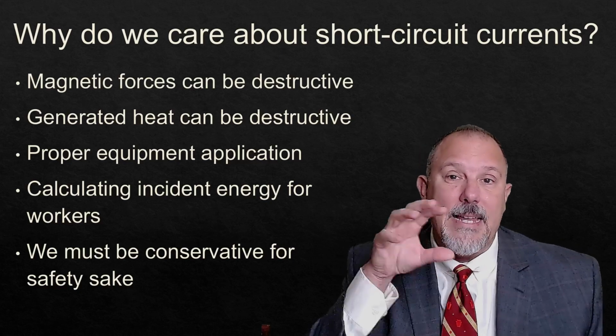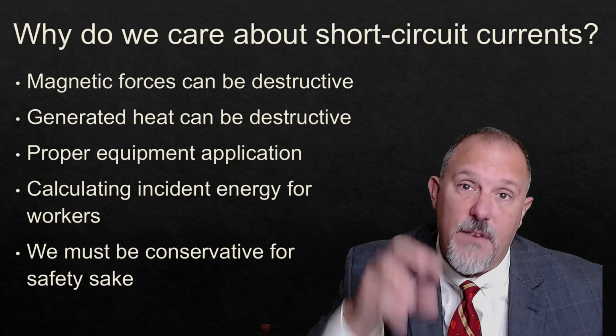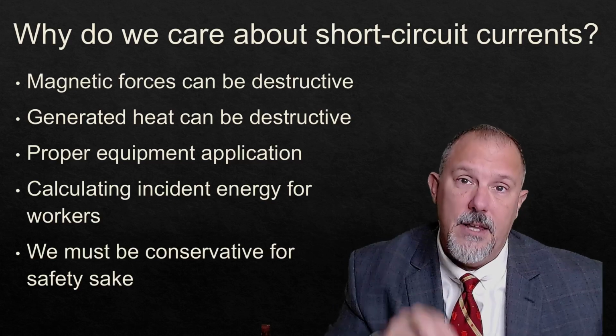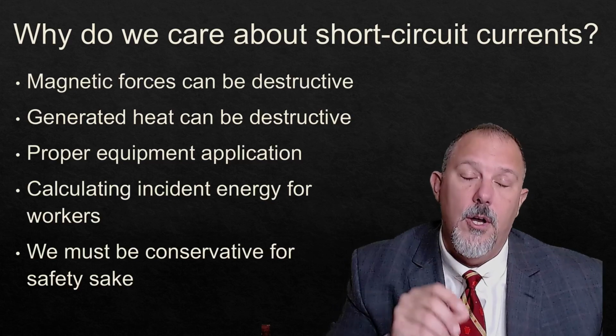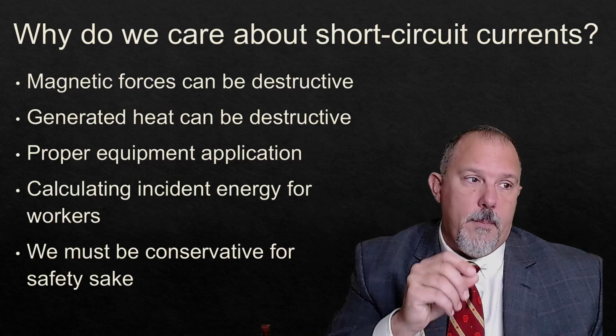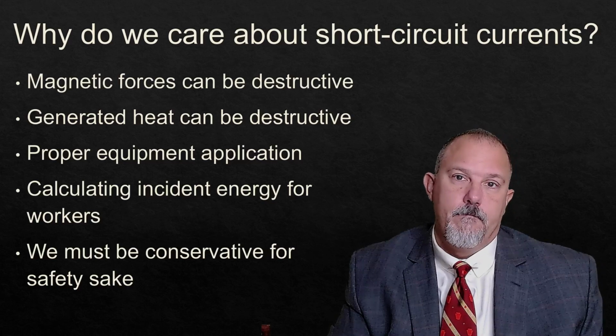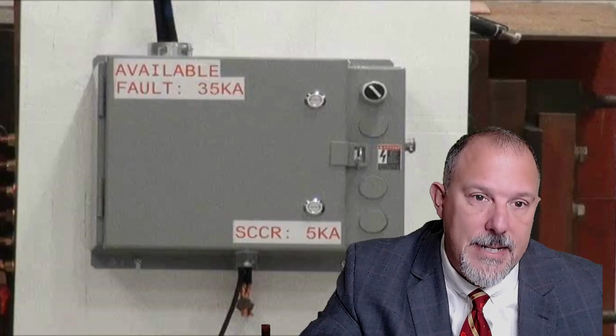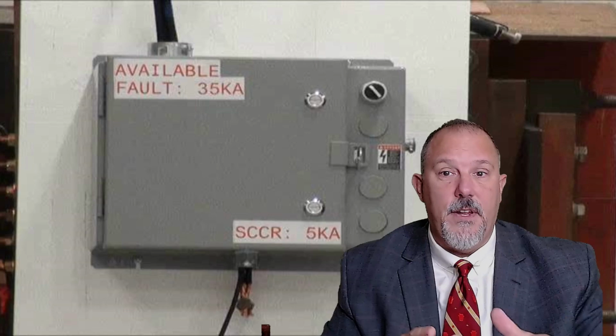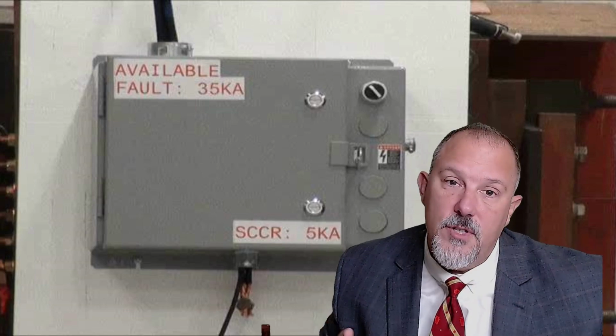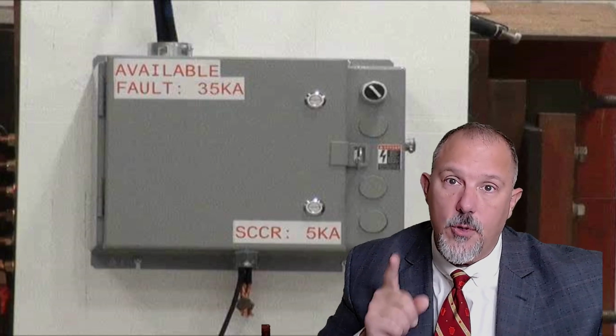So I need to calculate this. This is the most fundamental calculation that you can perform on a power distribution system, and it's important for us to understand it. This is a video of what happens when you exceed the short circuit current rating.